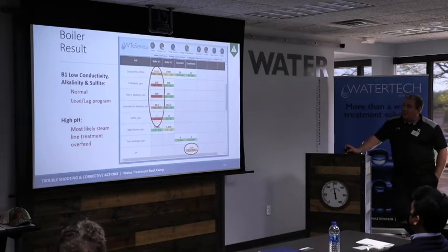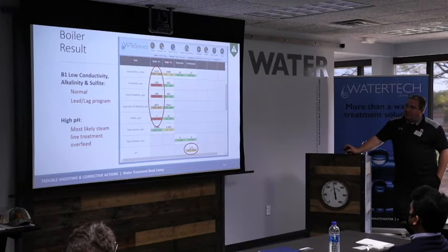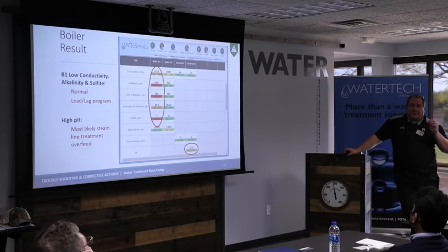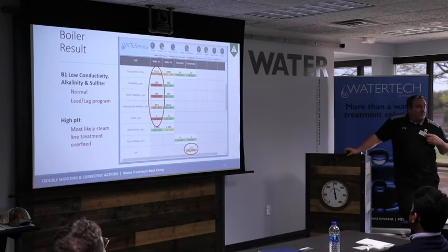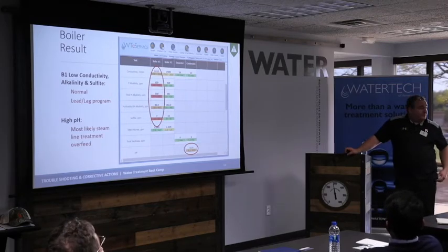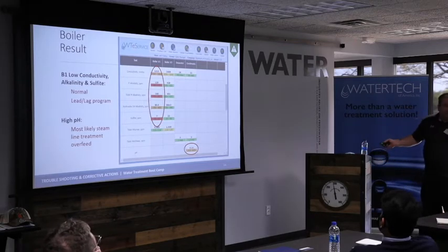Right? Well, then you probably have some type of water loss in here that just isn't allowing the boiler to get the chemistry in it. That's why. Because you can see when a boiler is running normally as it should, the numbers are all in range. So it gives you an idea that you're probably feeding your chemistry at the right rate. Because you got one boiler that's doing pretty good. The other one just isn't getting used or it's blown down too much. But this is actually lead/lag, so this is probably more normal than anything else. All right?